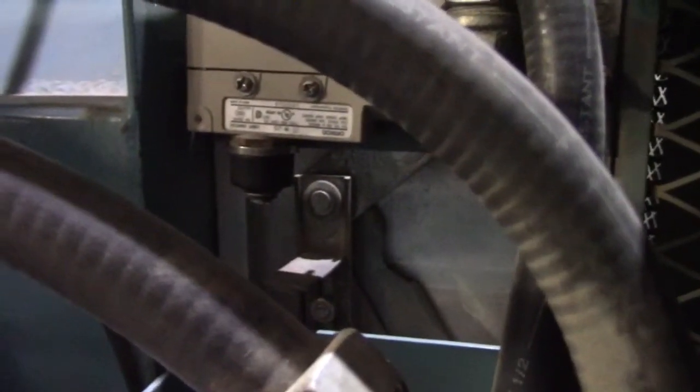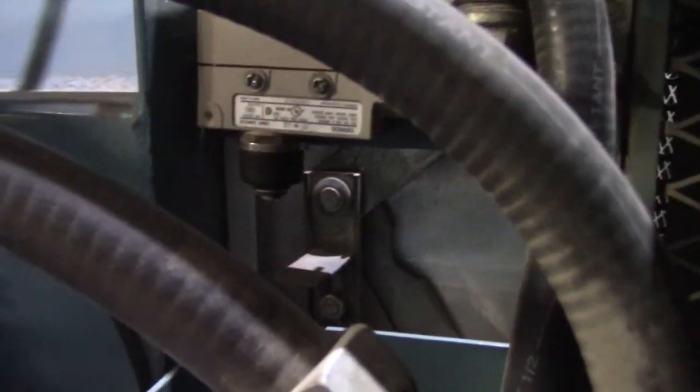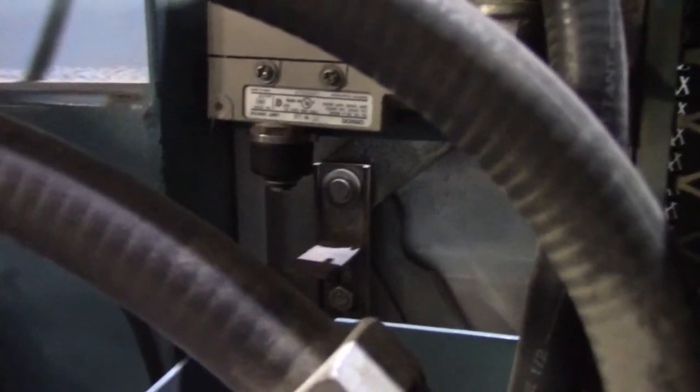It appears that this switch is not made. It looks like the damper is not moved to make this switch. Here's the switch. Here's the arm of the damper to push up on that switch to make it. So it appears that's probable. Well, I know that's definitely one of the things keeping this boiler from going into purge.